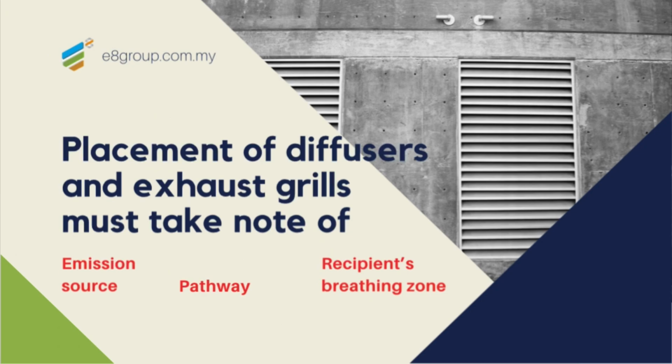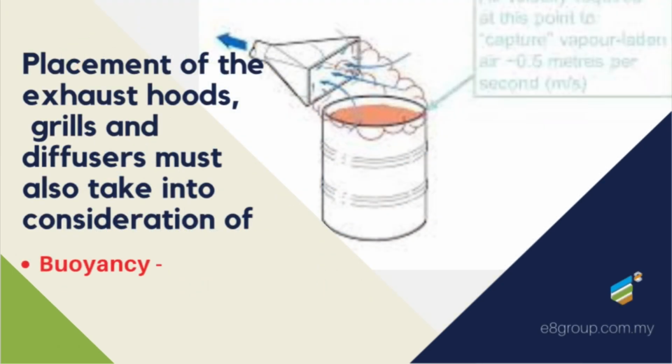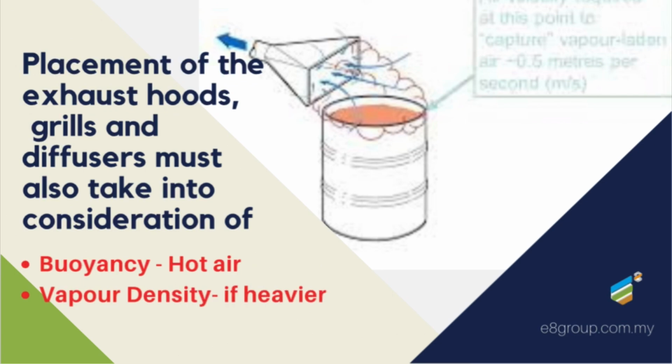But when you opt for general ventilation, or even when using LEV and GV, consider the movement of air. If your fume hood is going to be on the other end of the hall, ensure that your supply comes from the left side. Air movement happens from the left to the right. If your contaminant has higher density, depending on the specific gravity, it's a type of contaminant where even though it evaporates, it's going to basically suspend lower towards the floor, then your exhaust is going to be down, your supply is going to be top.